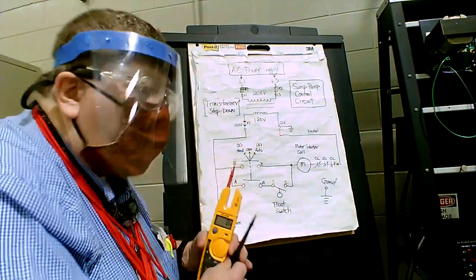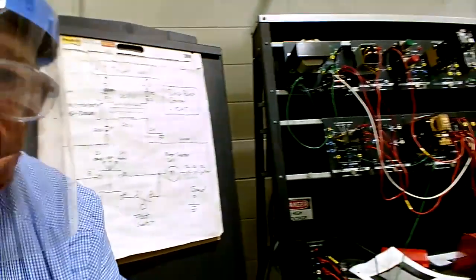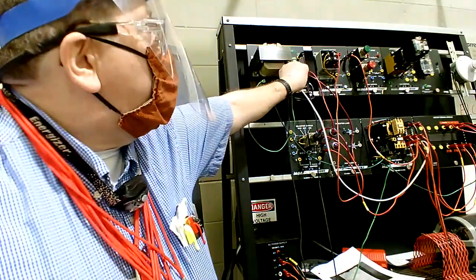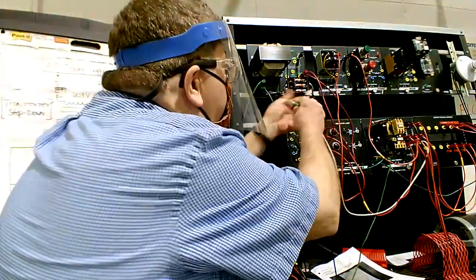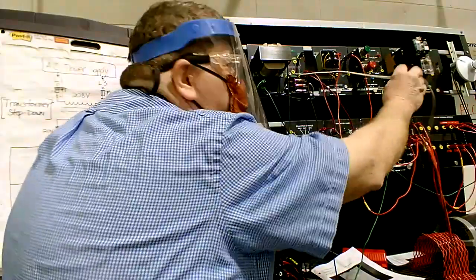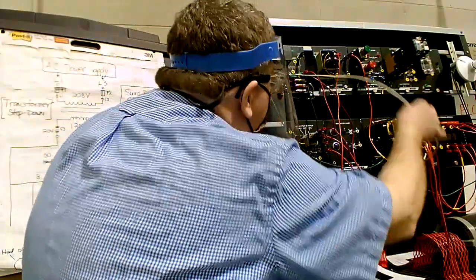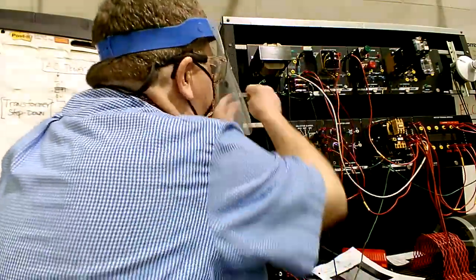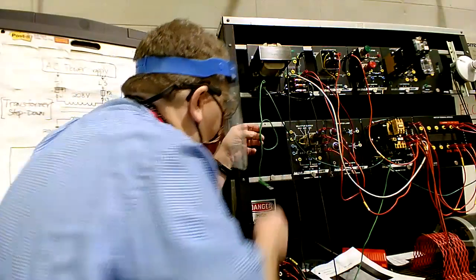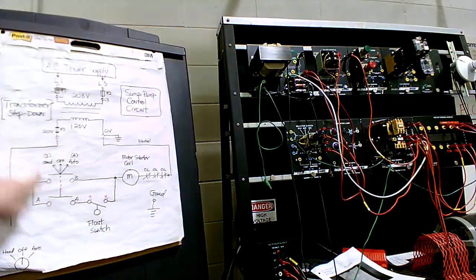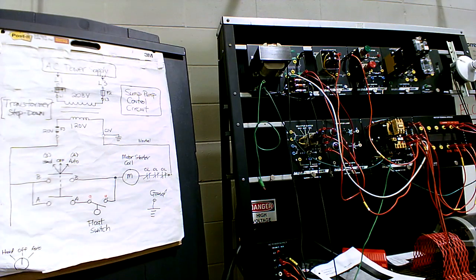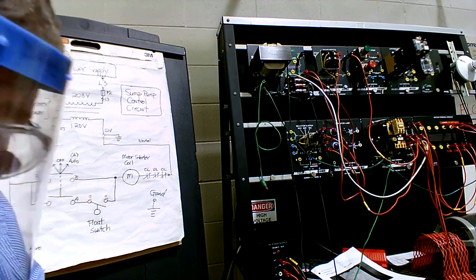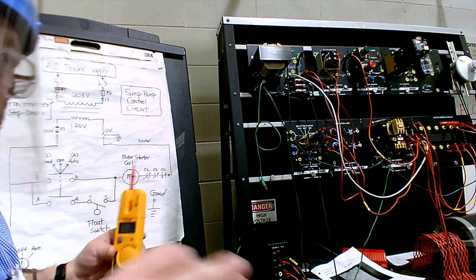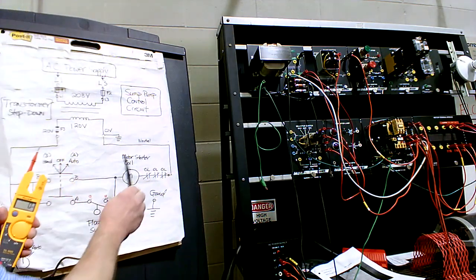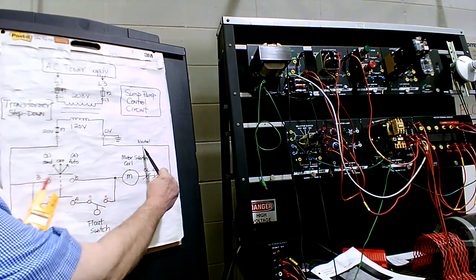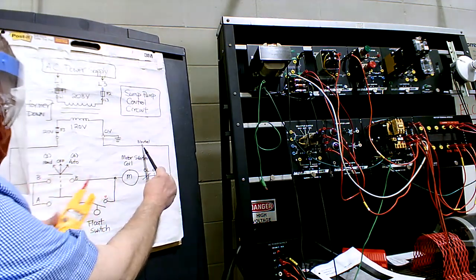Okay. Now, what happens if you go up here to this circuit and you disconnect the ground from the secondary, that neutral wire that comes in from the starter, from the coil, from the overload? If you do not ground it, then it's called floating. If you don't ground it, then the secondary, that 120 volt, is considered to be floating, not grounded. So when it's floating, here's what you have to do to get an accurate reading with your meter. Only one way. You have to go to the neutral wire with one lead of your meter and then test your signal with your other.